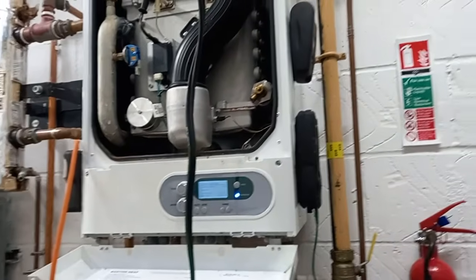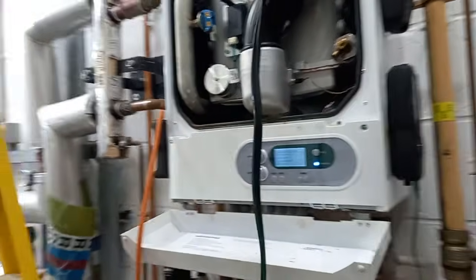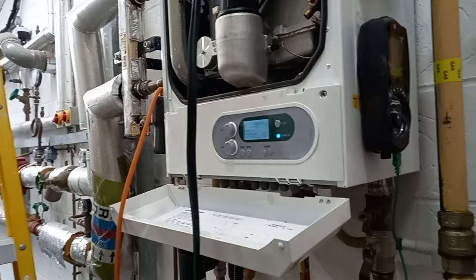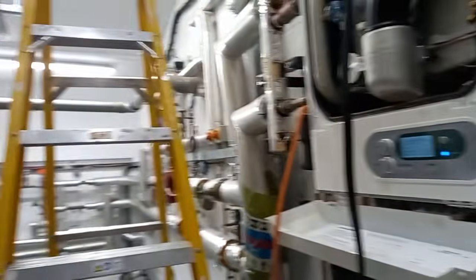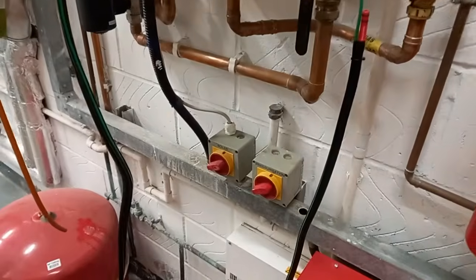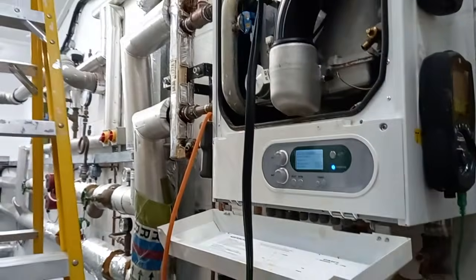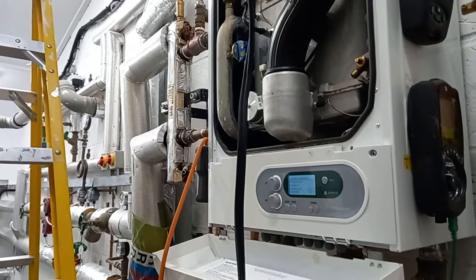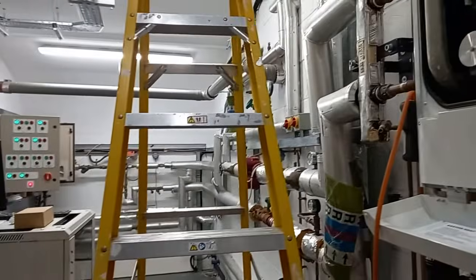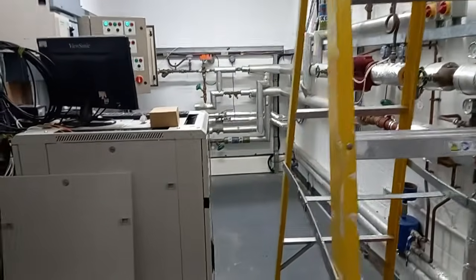And in this plant room, I can see that there's only one boiler. So there's more than one way I can turn a boiler off. I can just shut off the gas supply if I want, or I can go to the panel and turn it off. But sometimes when you switch it off from the main isolator, I don't know if this has ever happened to you before, but you've turned it back on and the surge in power can stop the boiler from working. So let's go over to the BMS panel.